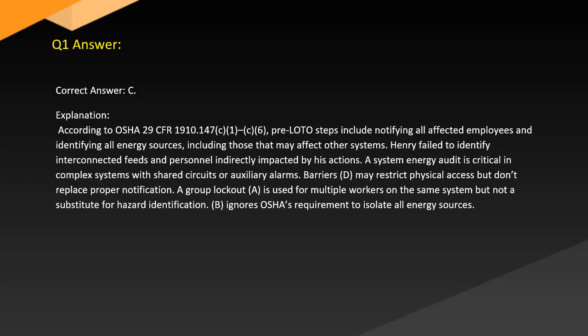Answer. Correct answer: C. Explanation. According to OSHA 29 CFR 1910.147 C1, C6, pre-LOTO steps include notifying all affected employees and identifying all energy sources, including those that may affect other systems. Henry failed to identify interconnected feeds and personnel indirectly impacted by his actions. A system energy audit is critical in complex systems with shared circuits and auxiliary alarms. Barriers, D, may restrict physical access but don't replace proper notification. Group lockout, A, is used for multiple workers on the same system but is not a substitute for hazard identification. B ignores OSHA's requirement to isolate all energy sources.